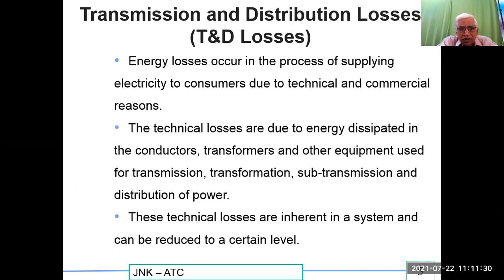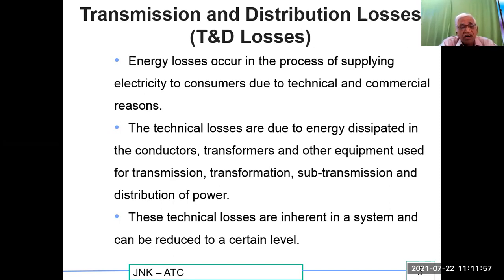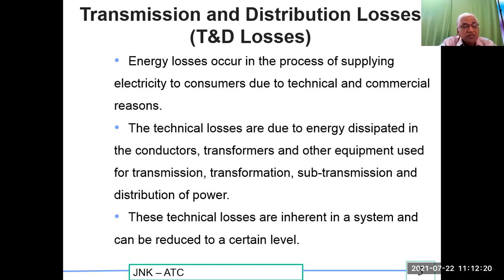Transmission and distribution losses, also called T&D losses: energy losses occur in the process of supplying electricity to consumers due to technical and commercial reasons. Technical losses are due to energy dissipated in conductors, transformers, and other equipment used for transmission, sub-transmission, and distribution of power. I²R losses occur in conductors; no-load and full-load losses occur in transformers. Low power factor draws more current, increasing I²R losses — our aim is always to maintain a power factor of at least 0.95 so we don't end up paying a penalty to the DISCOMs.